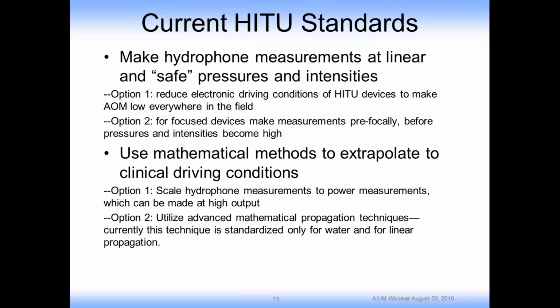So how do the current HITU standards address these issues? Well, first of all, the hydrophone measurements are to be made at linear and safe pressures and intensities. And there are two ways of doing that. The first option is to reduce the electronic driving conditions of the HITU devices that are being driven to make the acoustic output measurements low everywhere in the field, so you can scan throughout the field without these concerns. The second option is if you have, in particular, a focus device, you can make measurements prefocally before the pressures and intensities become very high.